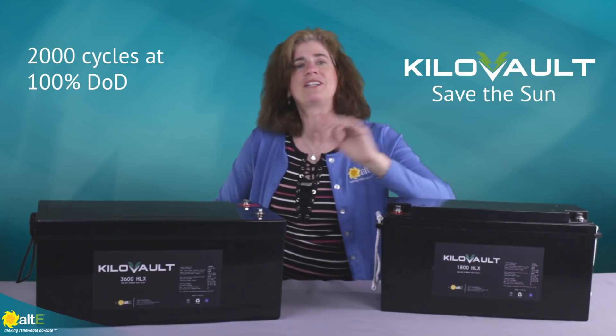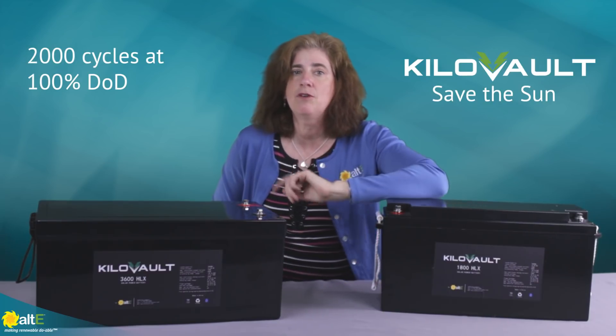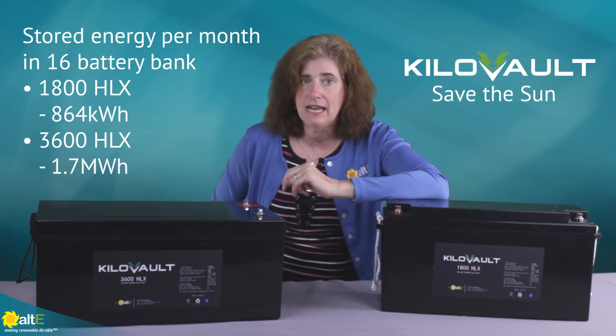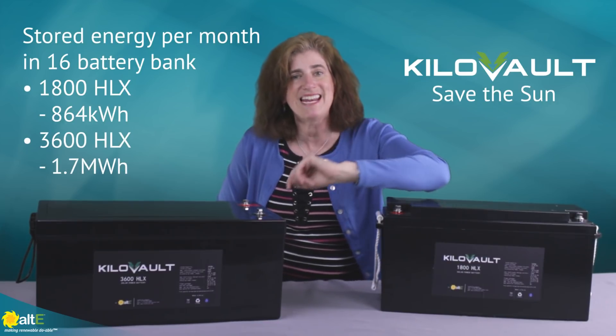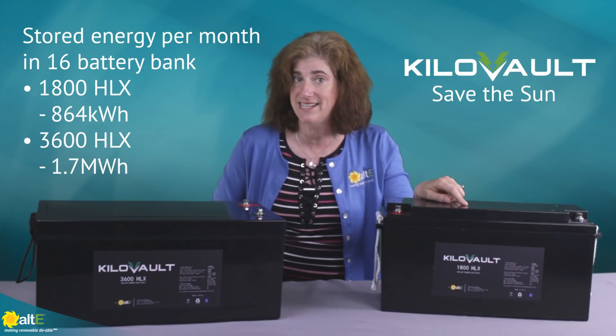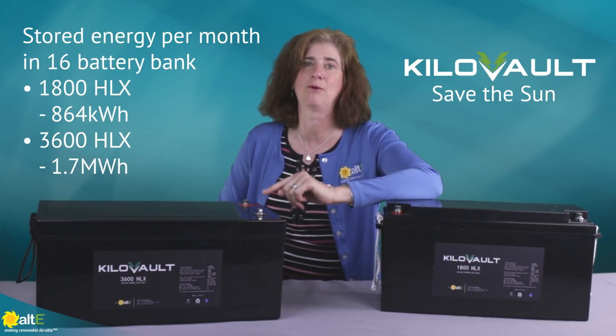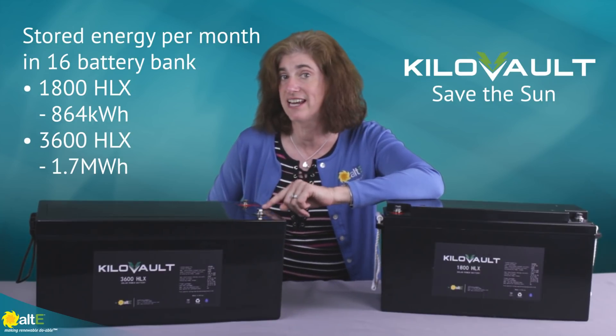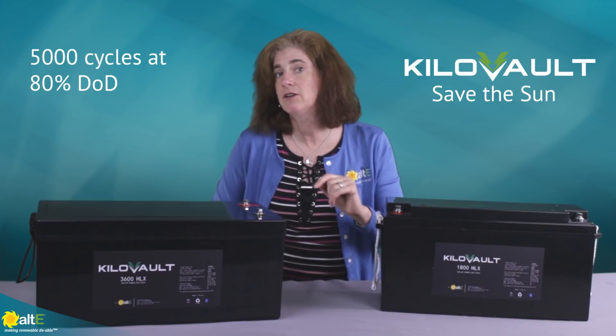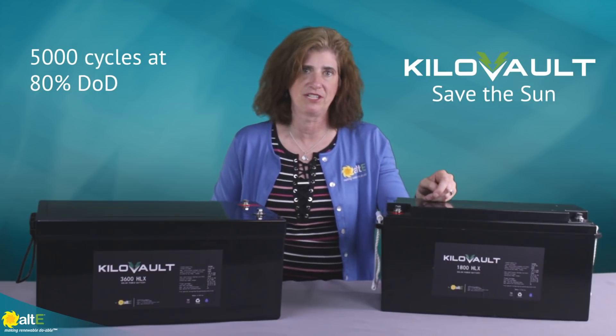The batteries can be discharged down to 100% depth of discharge without damaging them, giving you that full amount as usable capacity. At a monthly level, that gives you a maximum of 864 kWh for a full bank of HLX1800s, and over 1.7 MWh per month for a full bank of HLX3600s. However, for maximum cycle life, we recommend designing your KiloVault system for 80% depth of discharge.